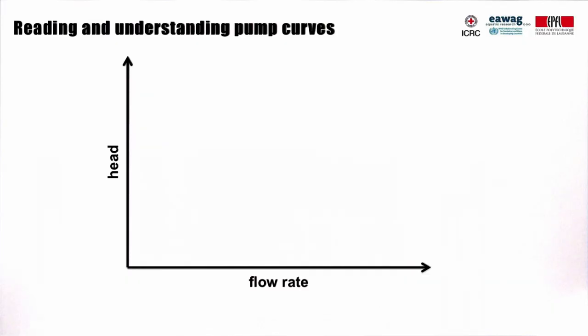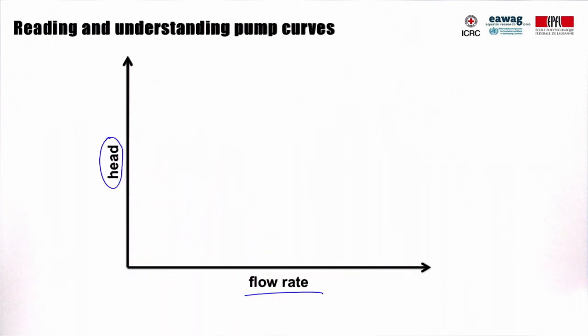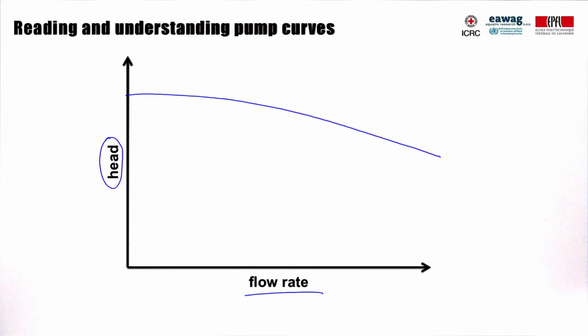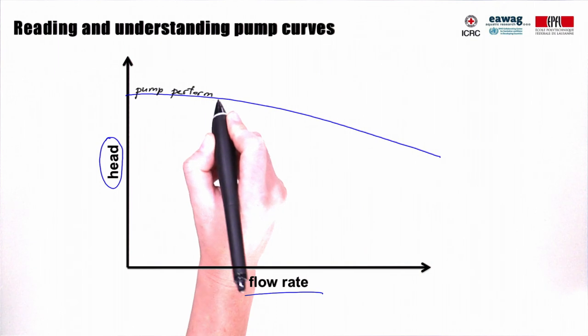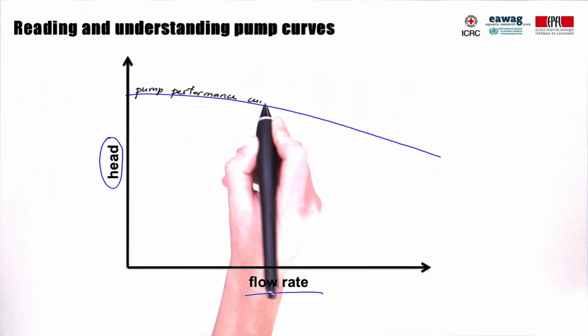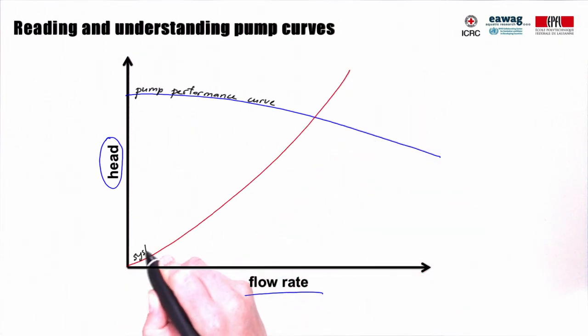That is why you need to read and understand pump curves if you need to choose and specify a centrifugal pump. A typical pump curve has two axes: the horizontal one showing flow rate through the pump, and the vertical one showing head, also sometimes called pressure. The first information we can read from any pump curve is the flow the pump will develop at any given operating head. This curve is also called the pump performance curve. Any piping system used to transport pumped water can be characterized by a head loss, which also depends on the flow rate of water in the system. Head loss will increase with flow rate. This red curve is called the system characteristics curve.